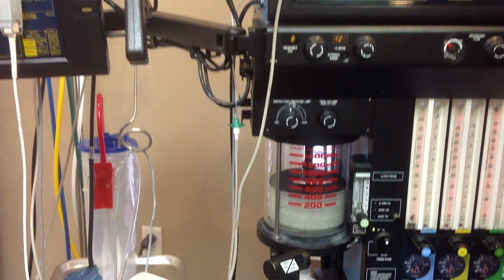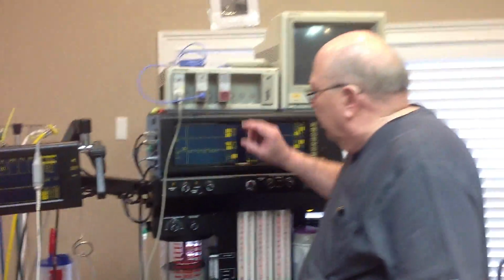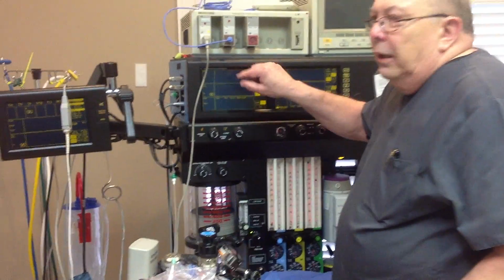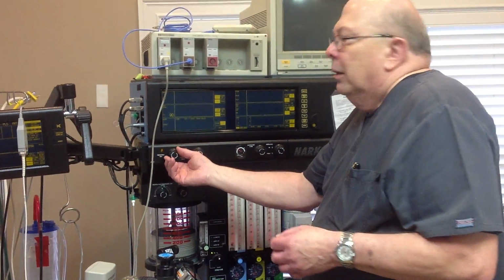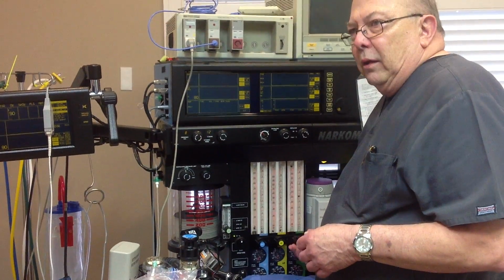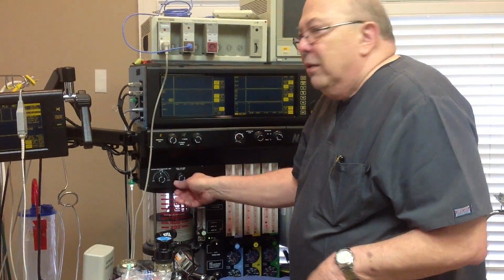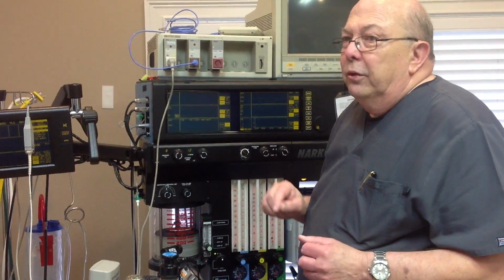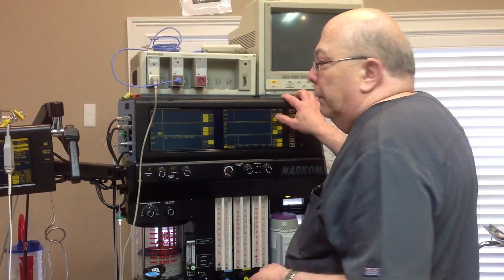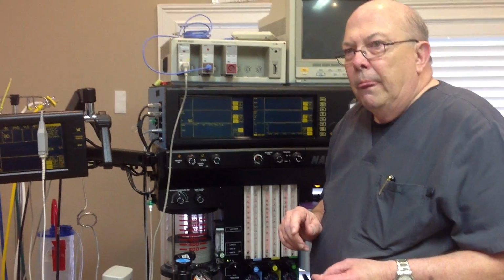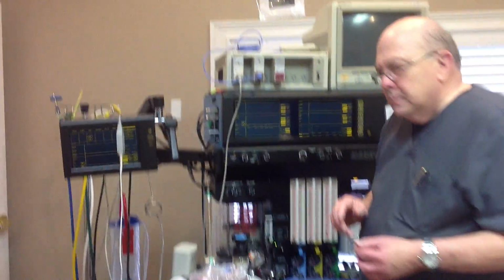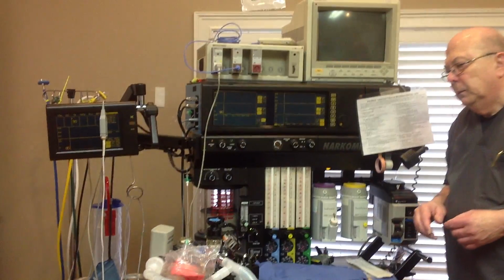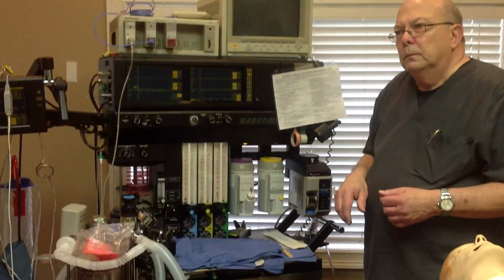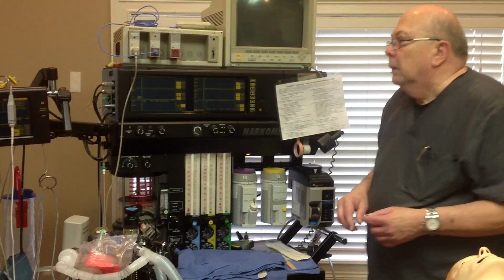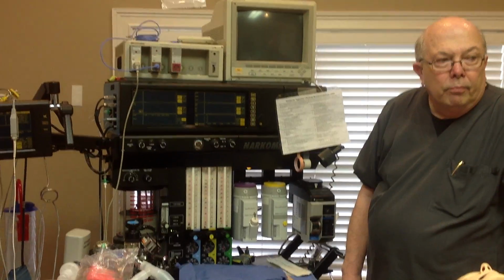So I'll preset that. Now it's not always going to be what you get delivered, because there's all kinds of things with the patient and all these other things that will happen. So you'll adjust your tidal volume and use your SaO2 and your end-tidal CO2 for your respiratory pattern. So you may have to adjust your rate. You may have to adjust your IE ratio. You may have to adjust your flow rates. And then you may have to adjust, once again, based on what your end-tidal CO2 is and what your SaO2 is. You just want something to get started with, because after you induce and get your endotracheal tube in, immediately you're going to check breath sounds, flip your ventilator on, and then you automatically know you have 8, 1 to 2, and about 700. So it gives you a second to get things situated, and then turn back and finesse it. But you know kind of where you have to start. And I do it the same way every time, so I know every single time I'm going to start with this and that, and then I go back and do all that.